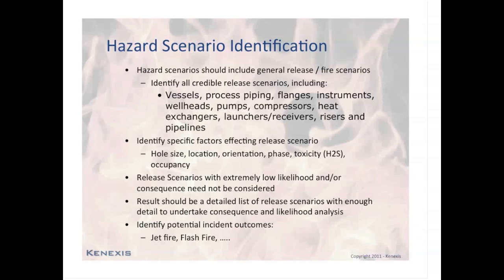After identifying all of the credible leak sources, we'll need to identify the specific factors that affect the release scenario or that define the magnitude of what we refer to as the source term in quantitative risk analysis. These include: what is the hole size, what is the location of the equipment, what is the orientation of the release, and what is the phase of the release? Is it a liquid? Is it a gas? Is it a two-phase release? And when the material is released, will it pool, and will that pool have a secondary vaporization term? We're going to need to consider the toxicity of the material and then also the occupancy of the area where the material is being released.